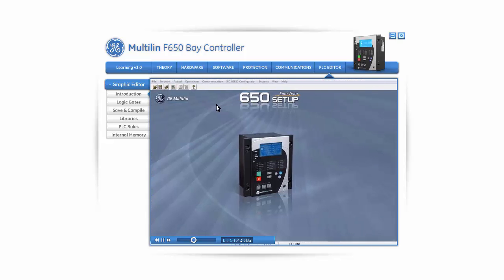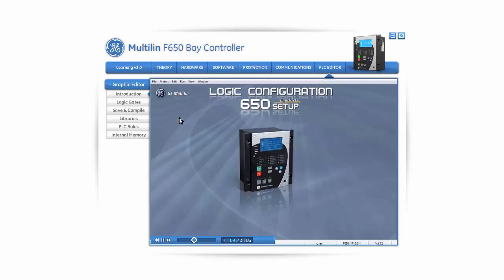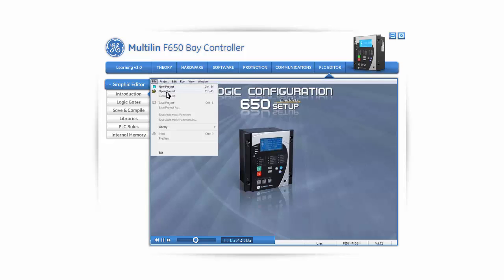Navigate to the Setpoint menu and select Logic Configuration. This will open a new part of the EnerVista 650 setup software — the 650 PLC Editor. Once in this new section of the software, open a graphical logic project using the menu File and then select the project of your choice. Alternatively, it is possible to create a new project, which would open up a blank canvas to start building your new logic.